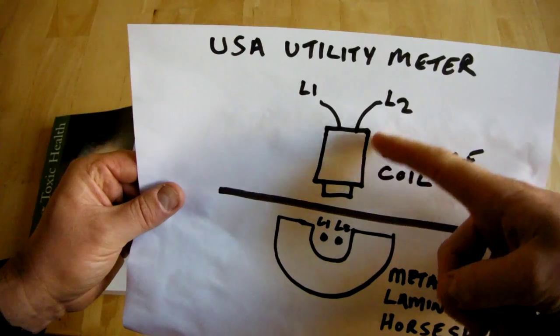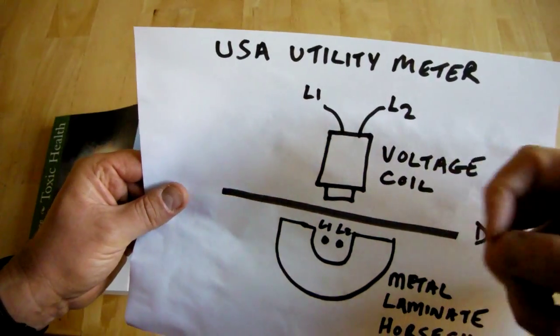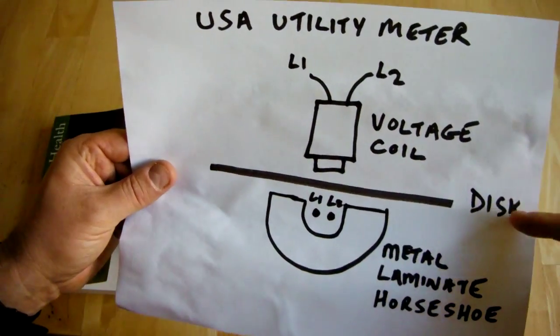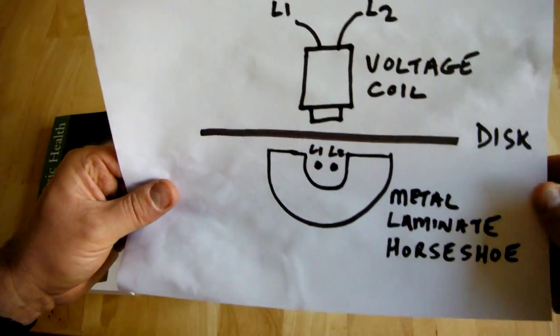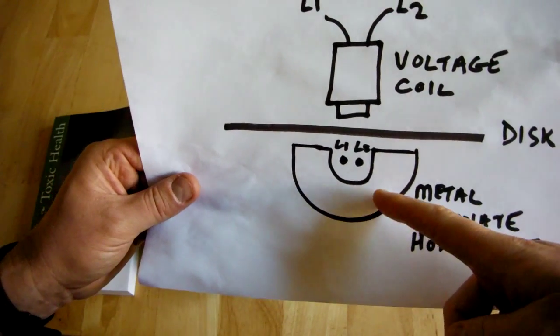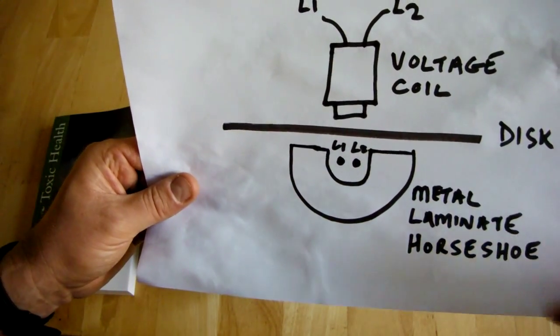So you find this voltage coil that is powered off live one and live two. And then you have this aluminum disc that is in the middle and that can rotate. And that aluminum disc is driven by this metal laminate horseshoe.